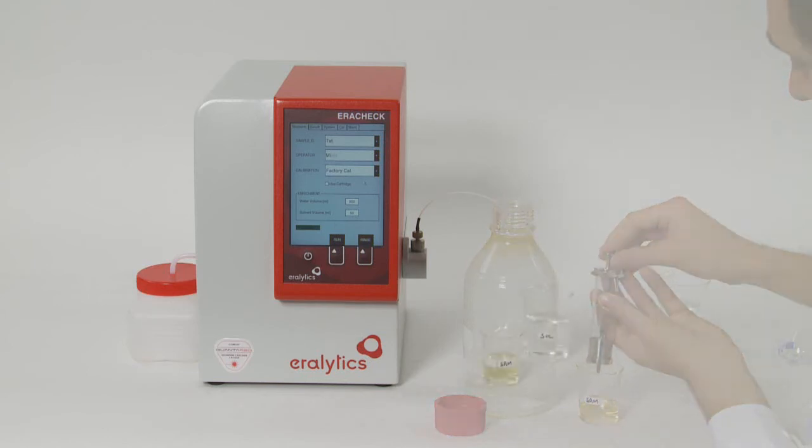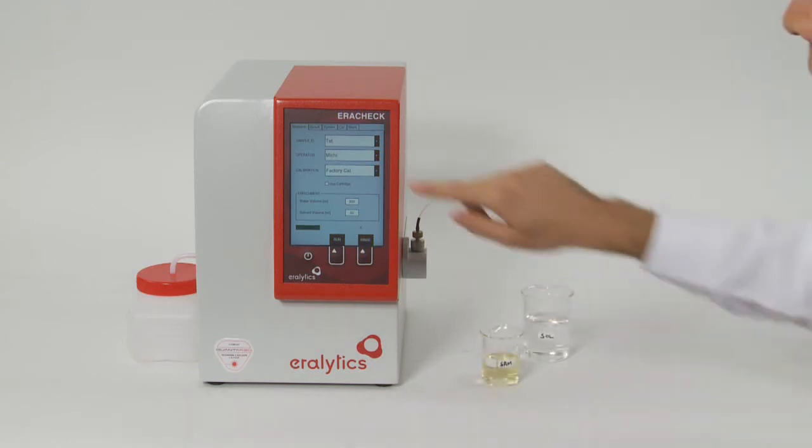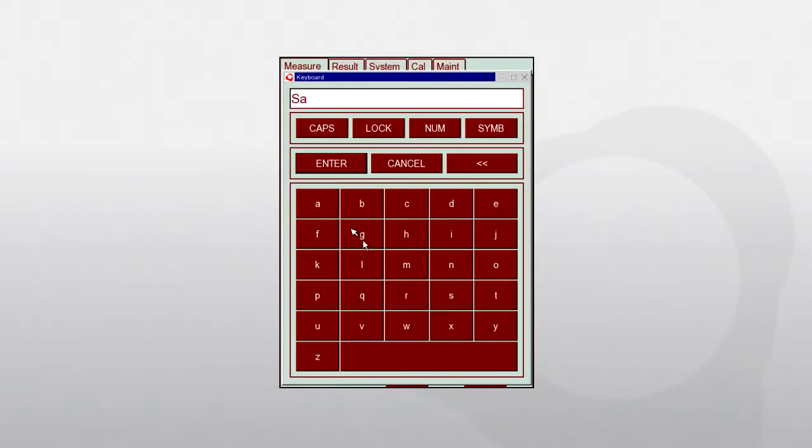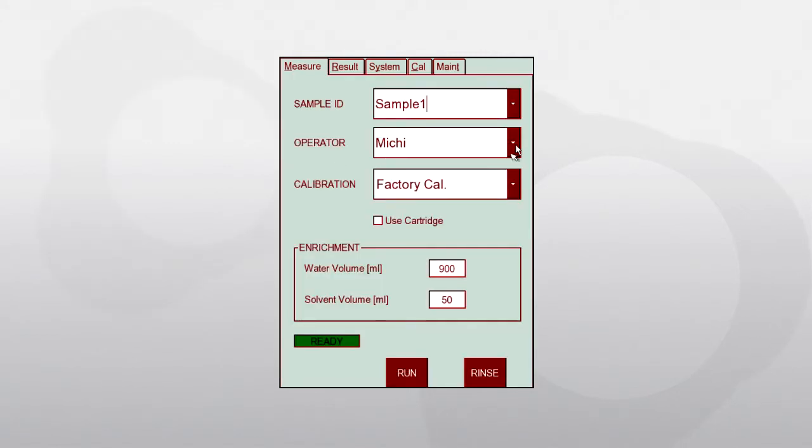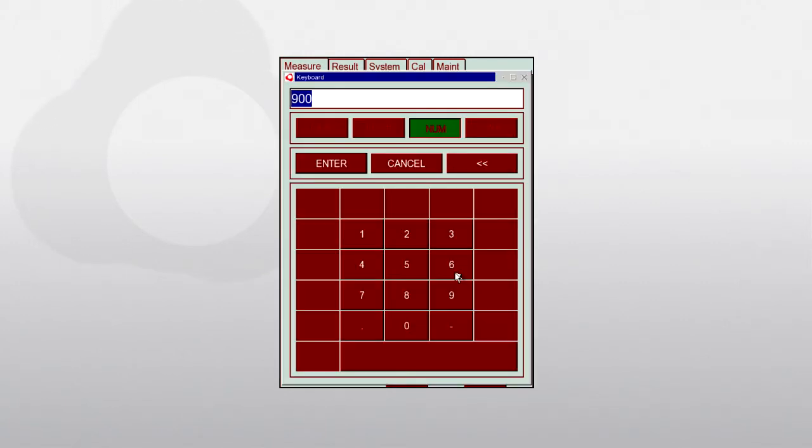Then use the delivered glass syringe to transfer approximately 20 milliliters of the top layer into a beaker glass. Now the extracted sample is ready for automatic analysis by the EraCheck. Enter the sample ID and the operator on the pop-up keyboard or select them from the drop-down list of previously entered names.